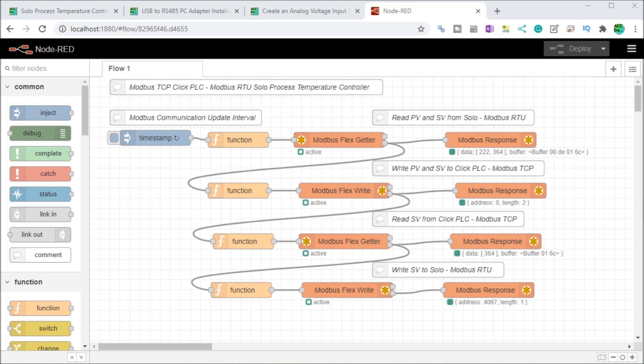In this series using Node-RED, we have previously installed the Windows software. We'll now continue to connect our industrial equipment to the Modbus protocol. We'll use the Node-RED contrib Modbus palette to communicate Modbus serial via RS-485 (Modbus RTU) to a Solo process temperature controller, and also use Modbus Ethernet TCP to communicate to a Click PLC. The present and set values will be read and written every 200 milliseconds, or five times a second.